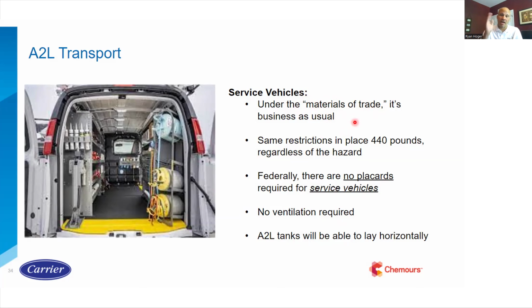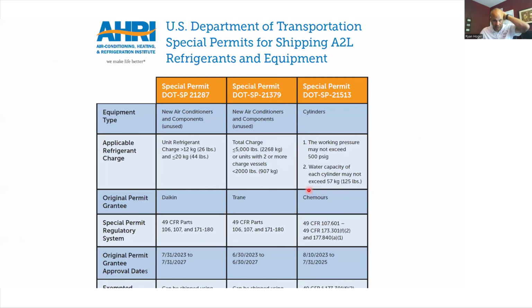But if you're driving down the highway with 300 pounds of refrigerant, materials of the trade service van guy, and there's a delivery truck right on your left hand side that has the exact same 300 pounds of the exact same refrigerant, he has to do placarding. You don't have to do placarding because you're a service van and he's a delivery guy. So it's just the way the rules happen to be. There are some other rules. Like we said, the refrigerant cylinders are 20 pounds for a reason. If you have larger refrigerant cylinders, then you have to go and do the placarding.